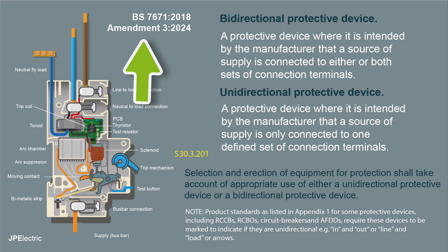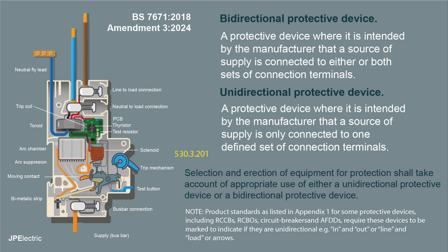This is in BS 7671, 2018 Amendment 3, 2024. There's been a bit of fuss about it. We have REG 530.3.201: selection and erection of equipment for protection shall take account of appropriate use of either unidirectional or bi-directional protective devices.